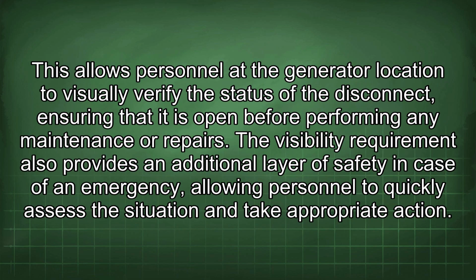This allows personnel at the generator location to visually verify the status of the disconnect, ensuring that it is open before performing any maintenance or repairs. The visibility requirement also provides an additional layer of safety in case of an emergency, allowing personnel to quickly assess the situation and take appropriate action.